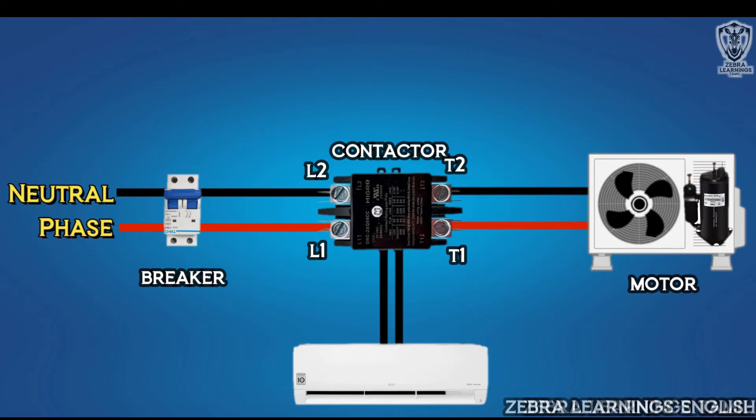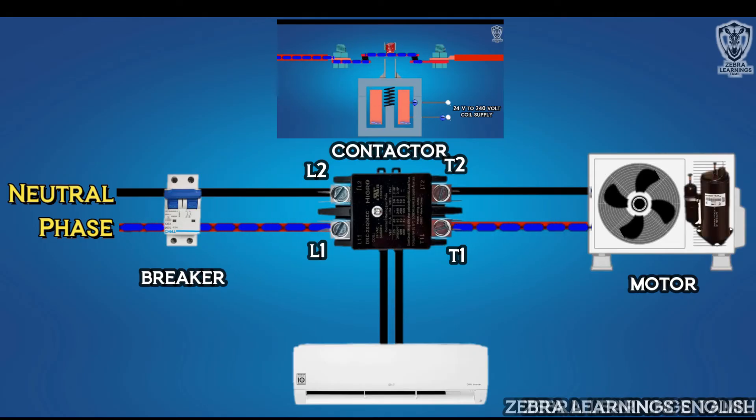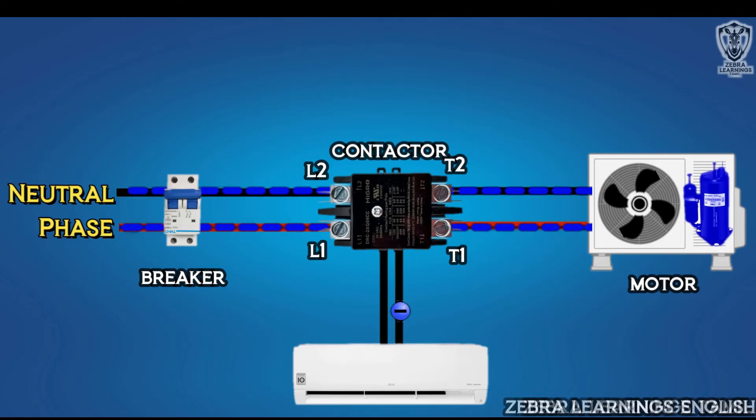After increasing room temperature, 24V power supply will come from the indoor unit to the contactor. Now the contactor energizes and creates an electromagnetic field that attracts the armature and closes the circuit. After the circuit is closed, the electricity from the main power supply goes through it and the compressor and fan motor run.